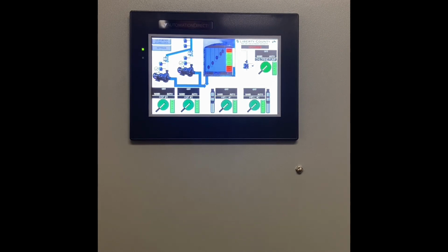Now, you'll also notice, we'll go back to our flow pressure switches, that I have 4 of them here, but only 2 of them have green check marks. Those 2 are the feedback for their respective high service pumps. If high service pump number 1 here is running and this pressure switch does not open within the allotted time from the settings screen, it will produce an X. When it produces an X, the pump will fail, and the other pump, as long as it is in automatic and ready, will start running. The other 2 pressure switches do a very similar function, but they do it for the wells when the system is in groundwater storage tank bypass mode. We'll cover more on that in a minute.